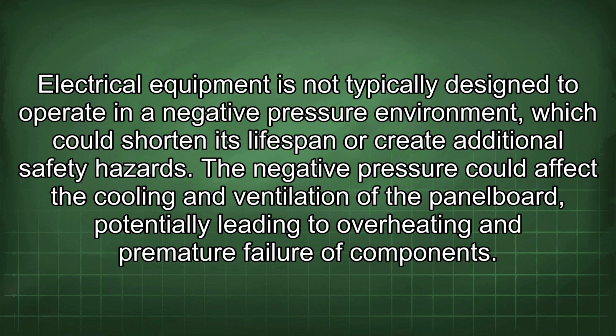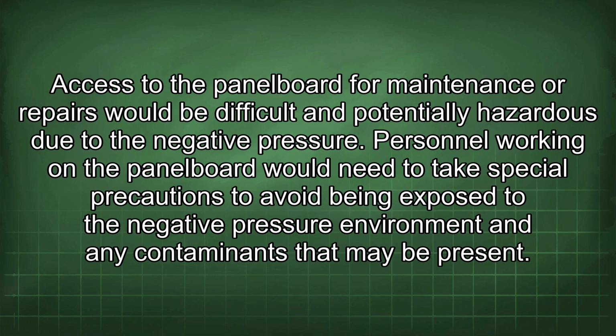Electrical equipment is not typically designed to operate in a negative pressure environment, which could shorten its lifespan or create additional safety hazards. The negative pressure could affect the cooling and ventilation of the panelboard, potentially leading to overheating and premature failure of components. Access to the panelboard for maintenance or repairs would be difficult and potentially hazardous due to the negative pressure. Personnel working on the panelboard would need to take special precautions to avoid being exposed to the negative pressure environment and any contaminants that may be present.